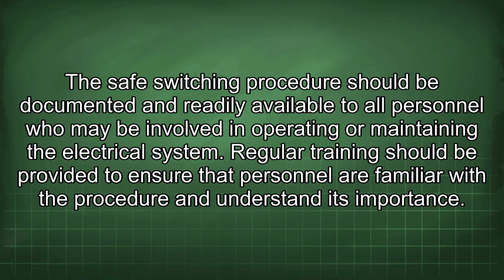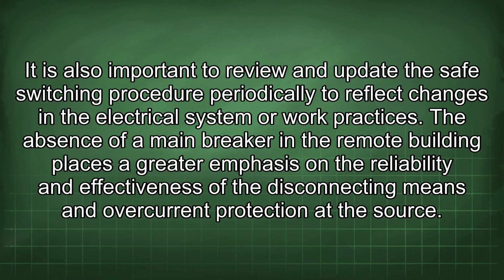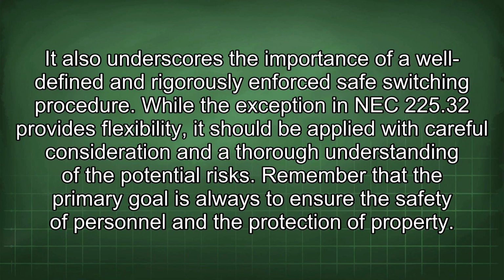The safe switching procedure should be documented and readily available to all personnel who may be involved in operating or maintaining the electrical system. Regular training should be provided to ensure that personnel are familiar with the procedure and understand its importance. It is also important to review and update the safe switching procedure periodically to reflect changes in the electrical system or work practices. The absence of a main breaker in the remote building places a greater emphasis on the reliability and effectiveness of the disconnecting means and overcurrent protection at the source. It also underscores the importance of a well-defined and rigorously enforced safe switching procedure. While the exception in NEC 225.32 provides flexibility, it should be applied with careful consideration and a thorough understanding of the potential risks.